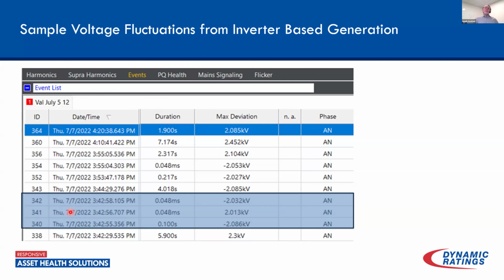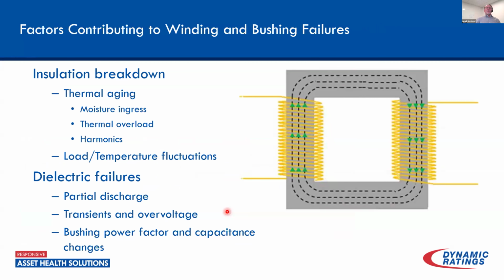Now, what I thought was interesting here for the voltage fluctuations, and again, this is that same power quality report that I was looking at before, is that within a very short period of time, these almost have the same time signature. We're about 350 milliseconds apart, and I went from a positive 2 kV to a negative 2 kV in a very, very quick period of time. So again, we're seeing very short duration, very fast changes in voltage, fast switching transients and things like that, all of which can impact that insulation, drive partial discharge, and basically increase that stress.